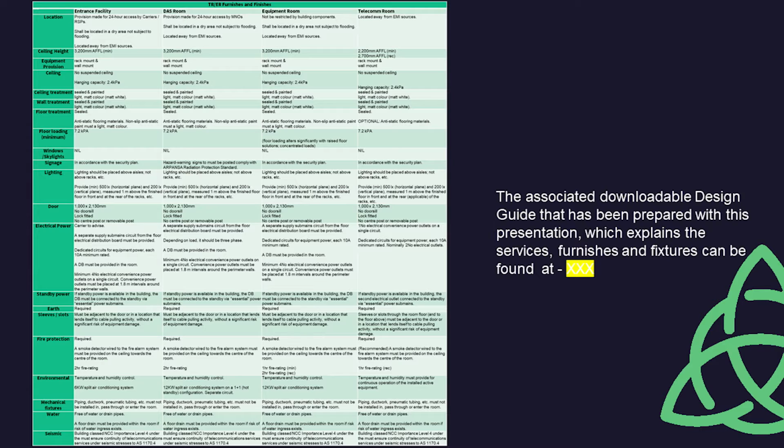There are two types of equipment rooms that are worth discussing separately. This is the carrier fixed telecommunications equipment room and the mobile network operator's DAS room. The carrier fixed telecommunications equipment room houses the carrier's entrance facility and any network equipment required by the carrier. This equipment room is often referred to as the entrance facility, which is not the correct term by the standards. Context is everything. The equipment room requirements are discussed in greater detail in Section 4 of ASNZS 3084.